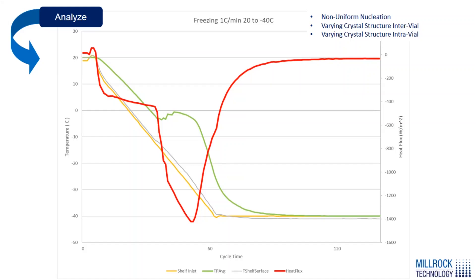These are the data results from our basic ramp freezing recipe. This red line is the heat flux measured from the vials, and the green line represents our average product temperature. The green line has a bunch of little jagged marks — each represents a single vial being monitored with a thermocouple nucleating spontaneously. These also correspond to dips in the heat flux as that vial nucleates and the temperature rises up close to 0°C.